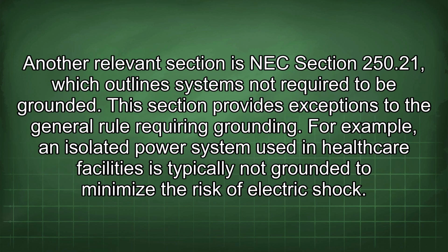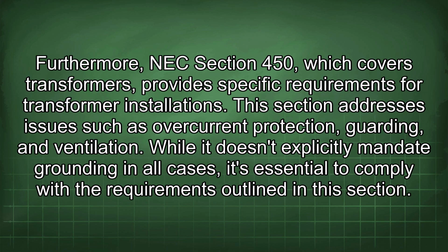Another relevant section is NEC Section 250.21, which outlines systems not required to be grounded. This section provides exceptions to the general rule requiring grounding. For example, an isolated power system used in healthcare facilities is typically not grounded to minimize the risk of electric shock. Furthermore, NEC Section 450, which covers transformers, provides specific requirements for transformer installations. This section addresses issues such as overcurrent protection, guarding, and ventilation. While it doesn't explicitly mandate grounding in all cases, it's essential to comply with the requirements outlined in this section.